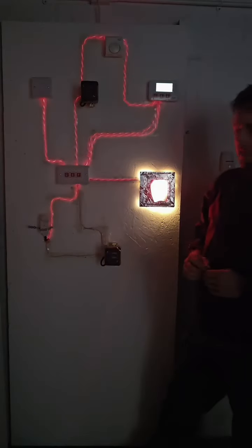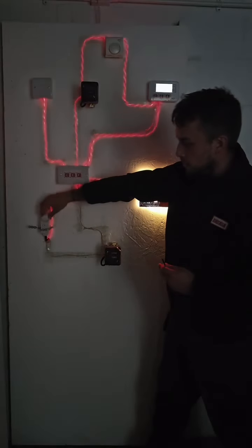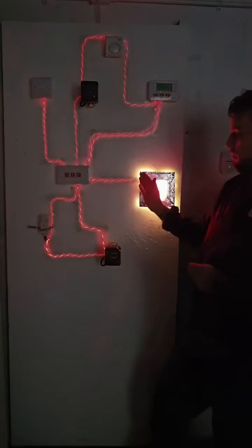with your hot water. It's sending the power down to your wiring centre, down to your hot water tank. But as you can see in this case, the stat is either set too low or your hot water tank is at temperature. So we're just going to ask that for more. So that is now asking the port valve to open, and only when this port valve opens, it will send the power back up to trigger the boiler.